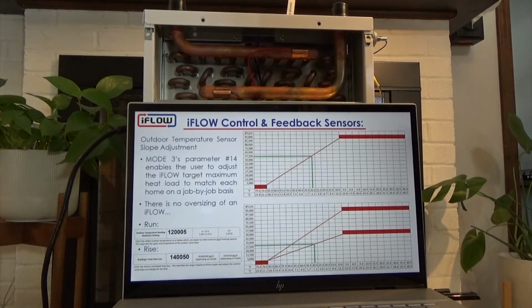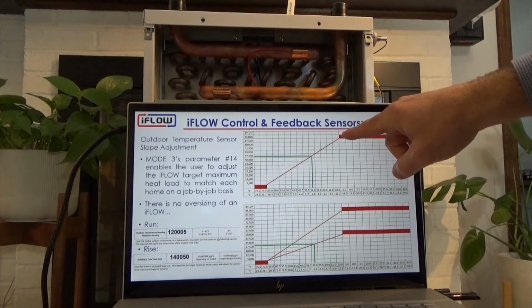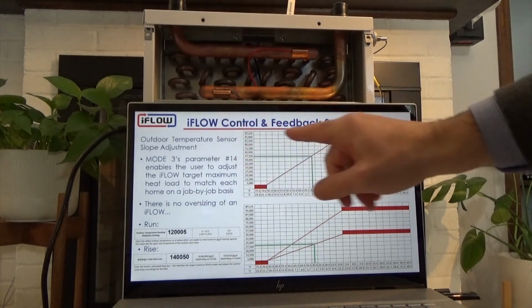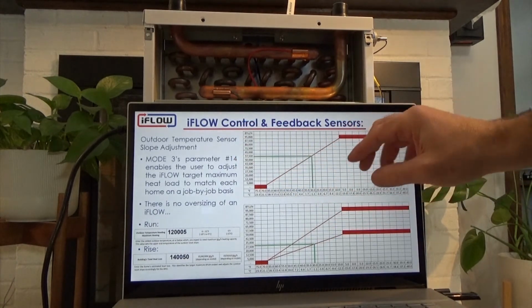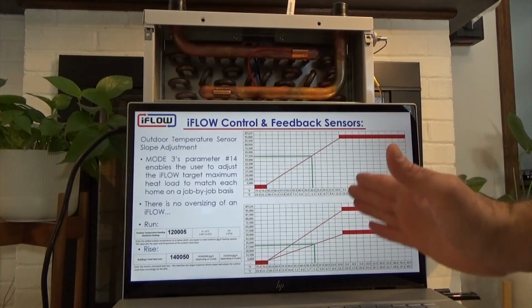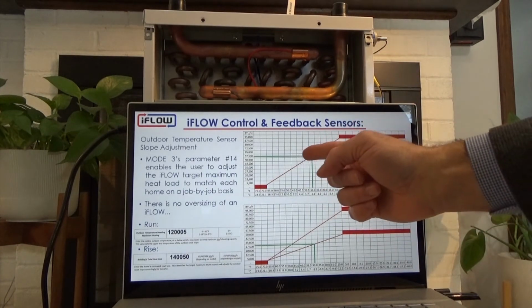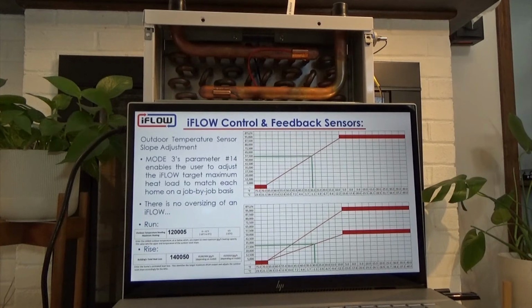So, why do we need the outdoor reset curve? Well, it's important because most of the year you don't need maximum demand. Even though we can deliver 95,000 BTUs, most of the season you need much, much lower than that. So why run at 95,000 when we only need 40,000 or 50,000 BTUs? And that's what that outdoor sensor does.